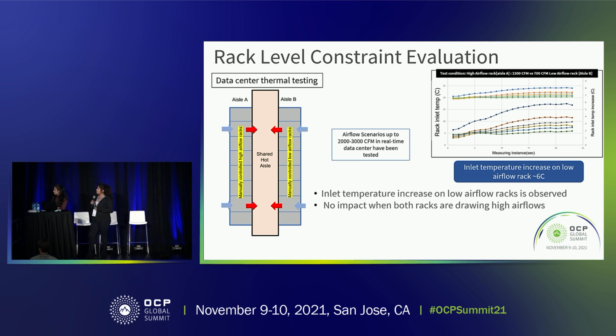And we manually controlled the rack fans such that on one side there are high airflow racks, and on the other side there are low airflow racks. We have done the test for airflow ranges between 2,000 and 3,000 CFM. And I am showing a specific data point here for, say, a rack with 2,300 CFM on the high airflow side and 700 CFM on the low airflow side. What we saw is that the low airflow rack has seen an increase in inlet temperature by 6 degrees Celsius.